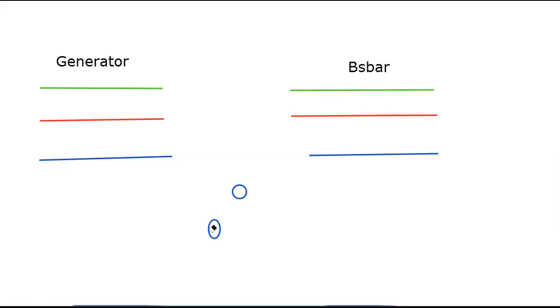We have three bulbs. These bulbs are connected to the lines as a backup for monitoring the synchronization. The main synchronizing equipment is called the synchroscope. If you lose that, there must be a backup way. The backup way uses a very simple method, using three lights.